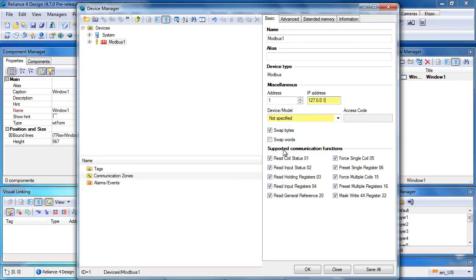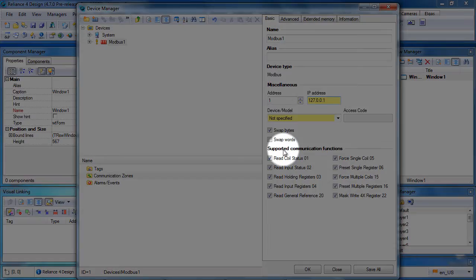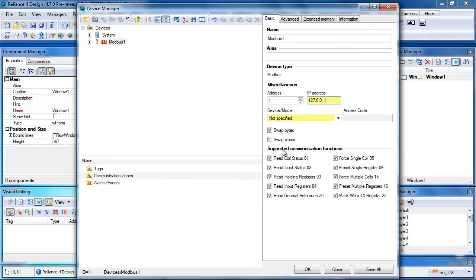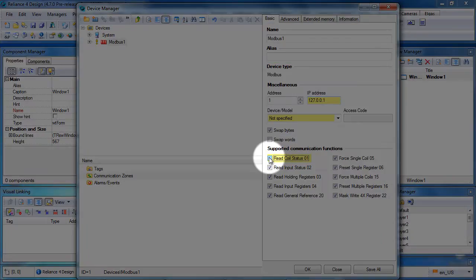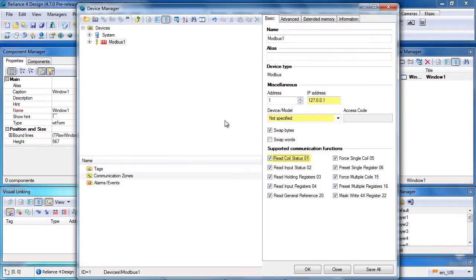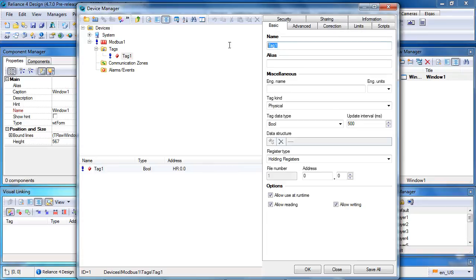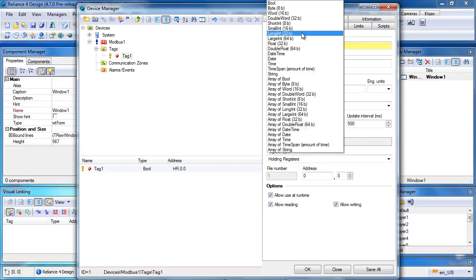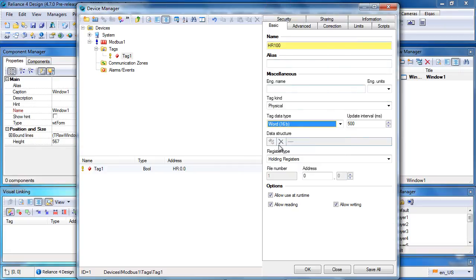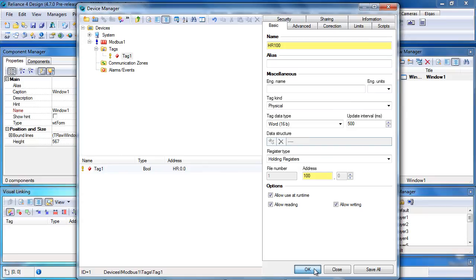If your Modbus device does not support any of these functions, it can be disabled. We need to create a new tag named HR100, set its data type to Word, register type to Holding Registers, and address to 100. We need to confirm the settings by pressing OK.